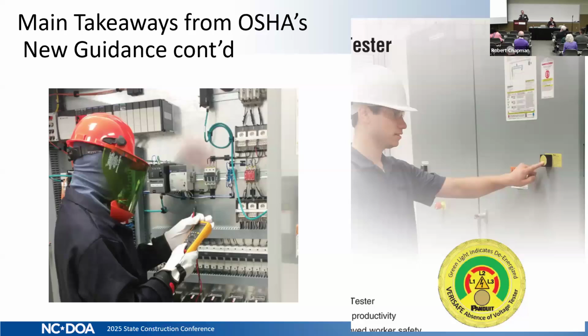So after you turn off the switch or the breaker that's feeding this panel and put your lockout and tagout on it, after you open the door, then based on the incident energy on this panel, you have to don the appropriate equipment, bring your multimeter up to it. And actually what the procedure says is you take that multimeter and you test it individually just to make sure it works, apply it to the equipment that you're going to maintain, make sure it's dead, and then you take it to something that you know is live and you put it on that. So it's live, dead, live. You have to follow that process wearing the PPE the whole time before it meets OSHA's criteria for being totally de-energized and in a safe working condition.